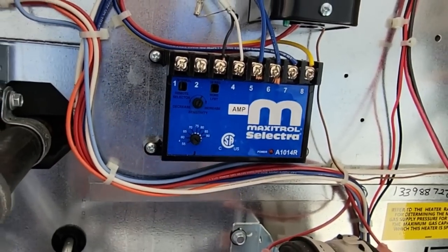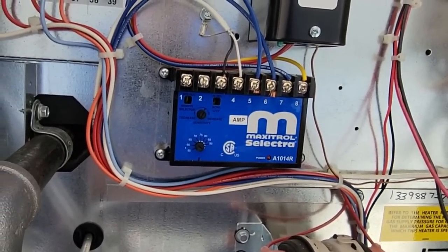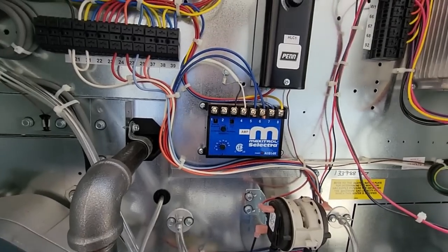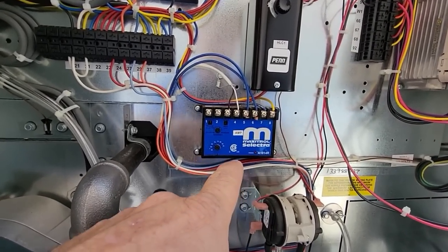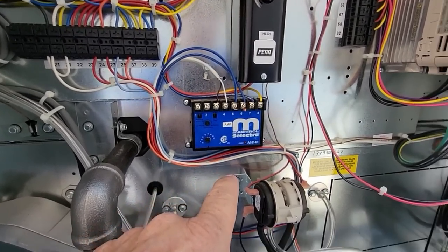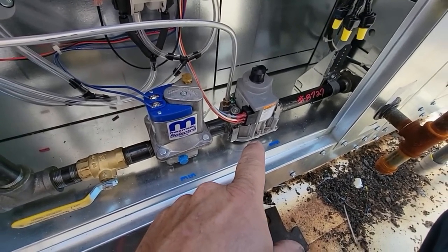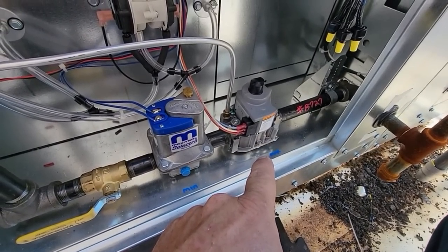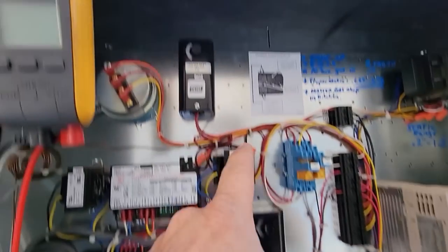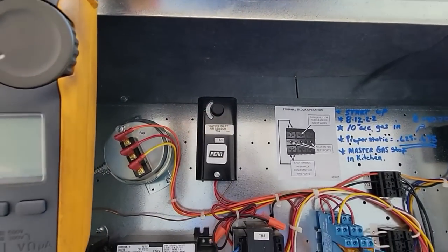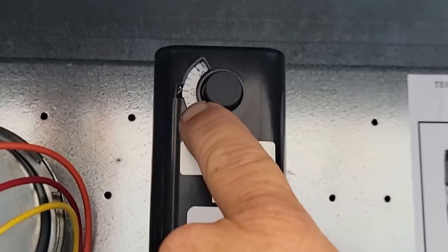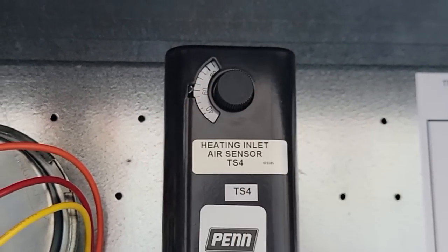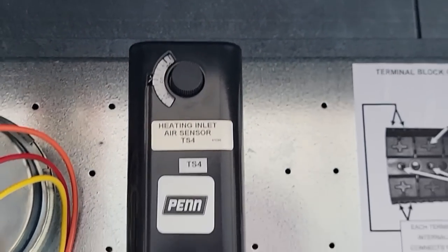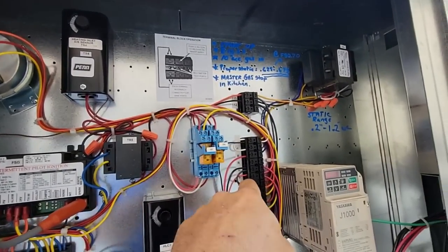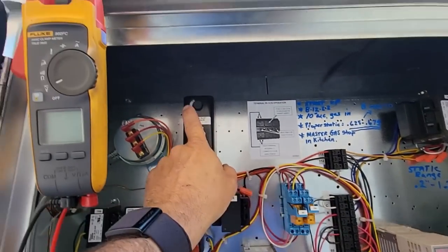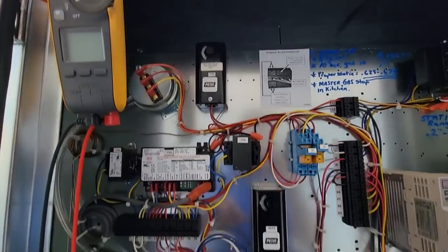In a kitchen, the last thing you want is hot air blowing on you. So that kind of is a double backup there. You've got the air never getting above 65 coming out. You've got your maximum down here set so that it can't be more than a 70 degree rise no matter what. You've got your outside air setting adjusted so that it won't even run unless it's at least 60 or 55 degrees. I'm gonna set it at 60. That can always be adjusted later. So it's always calling for heat, but unless this closes, it's not going to run.